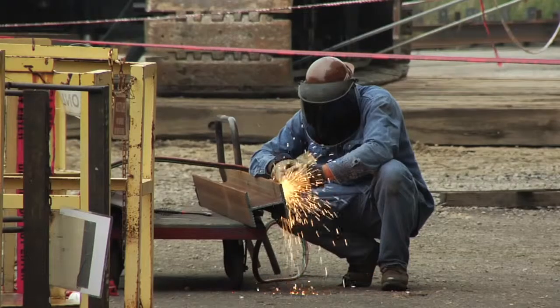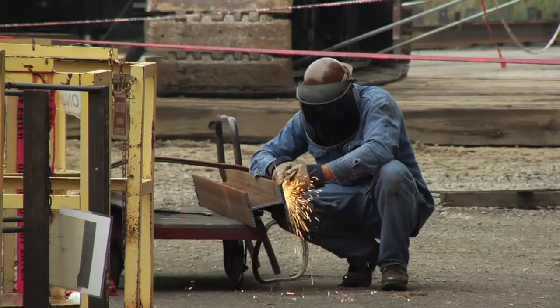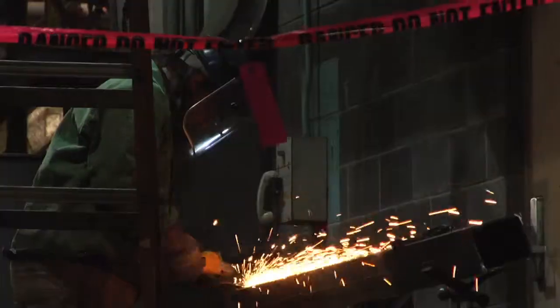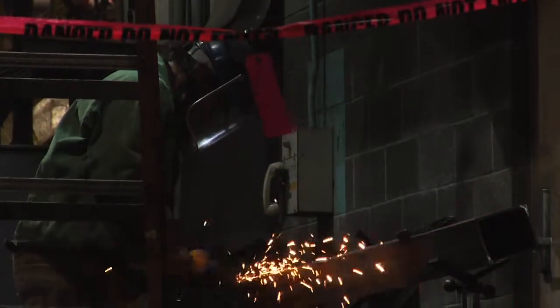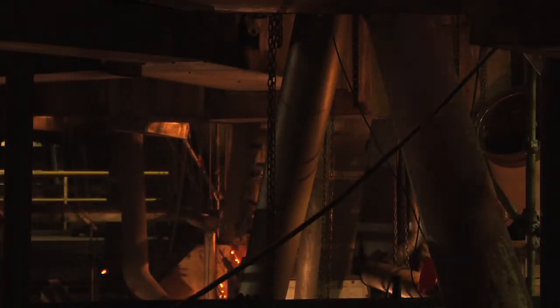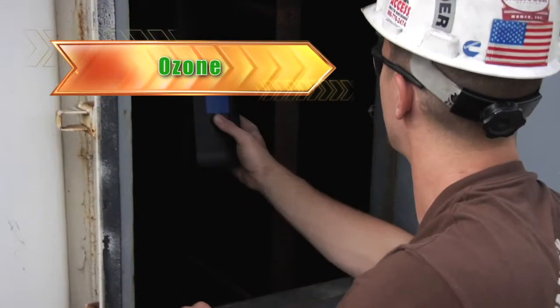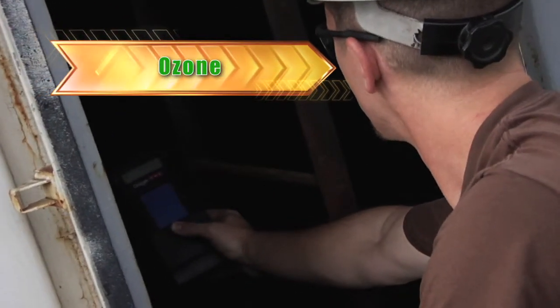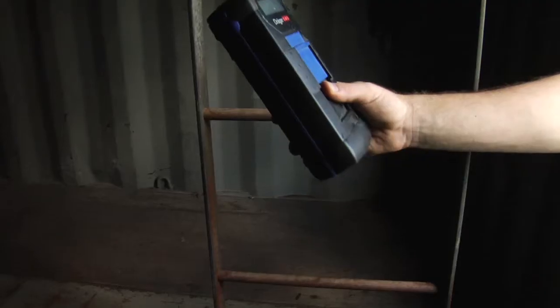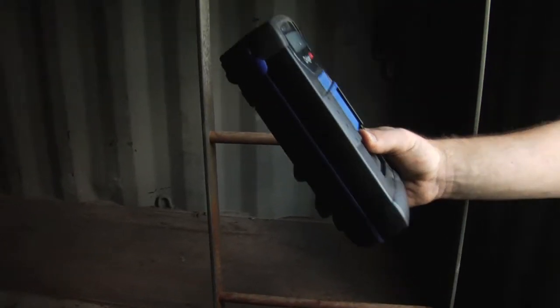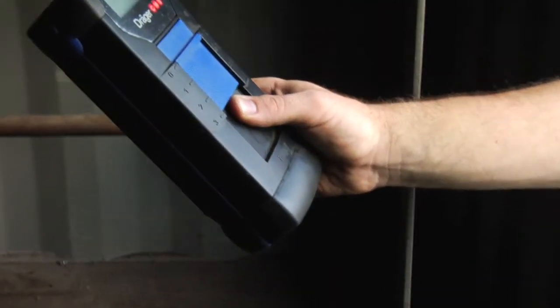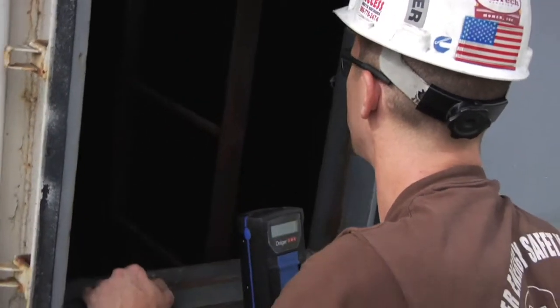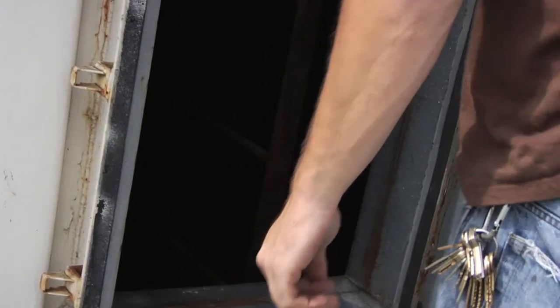If the permit requires a fire watch, then the fire watcher shall be trained and dedicated to fire watch. All flammable and combustible material must be properly guarded or removed within a 35-foot radius. Fire watchers shall remain at the worksite for 30 minutes following completion of the hot work. Contractors must conduct air monitoring for ozone prior to entering the boiler, ductwork, fans, or any part of the gas path with electrostatic precipitators in operation. Monitoring must continue while work is being performed in those areas. Contractors must provide their own monitoring equipment.